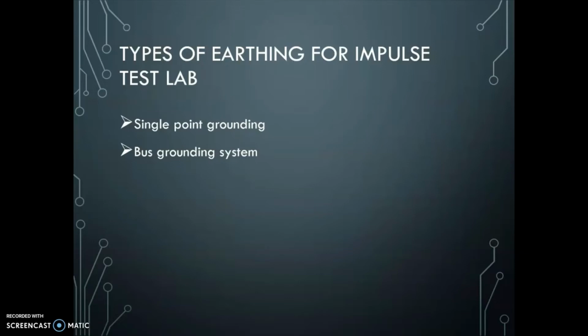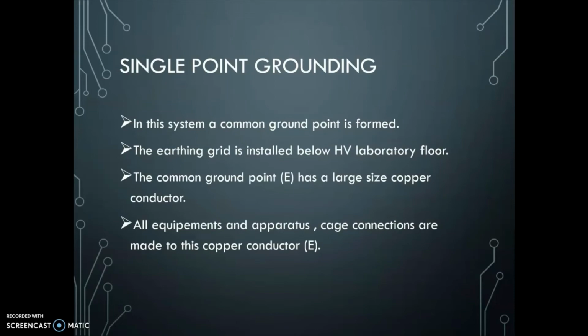Now talking about the first method, the single point grounding system for an impulse test lab. In this system, a common ground point is formed. The earthing grid is installed below the HV laboratory floor. The common ground point E has a large size copper conductor. All the equipment and apparatus cage connections are made to this copper conductor.